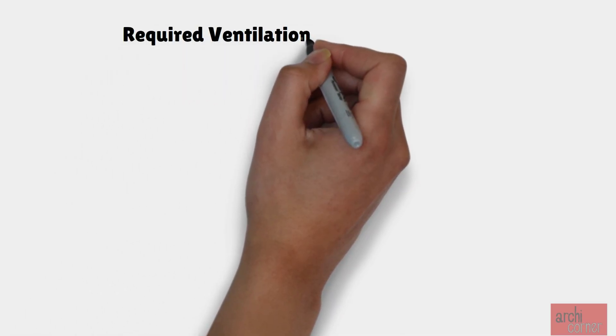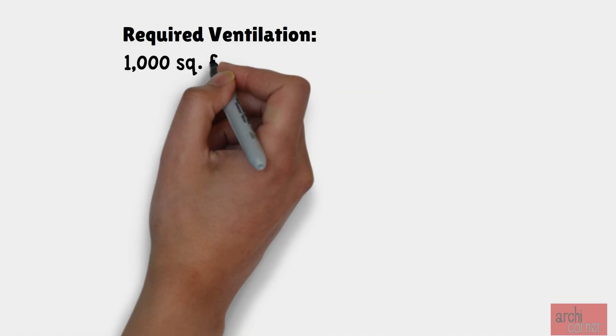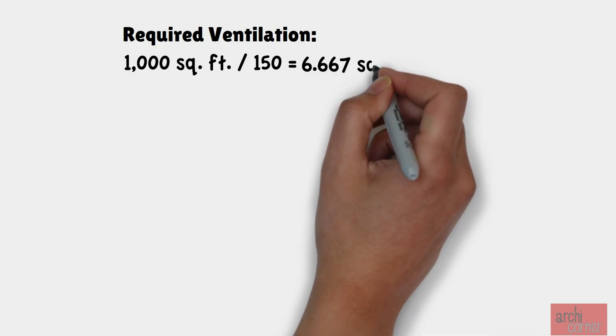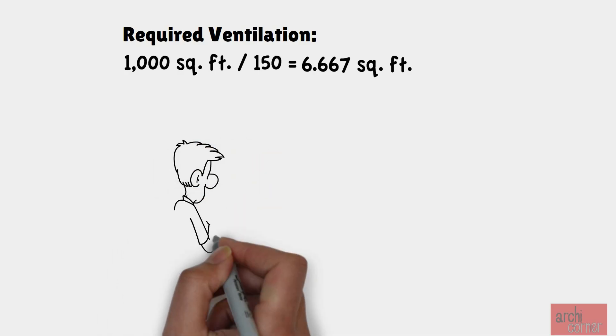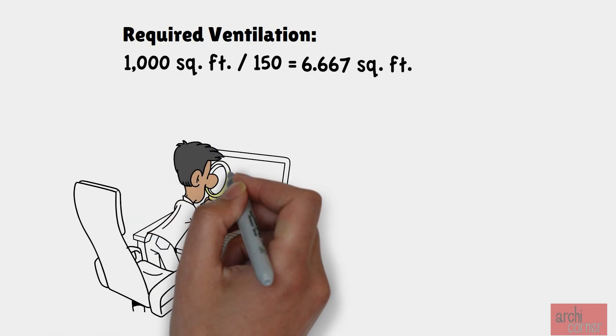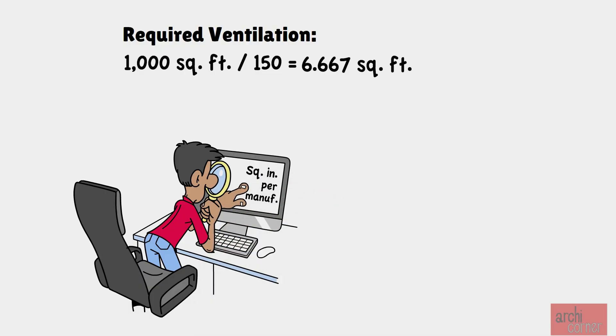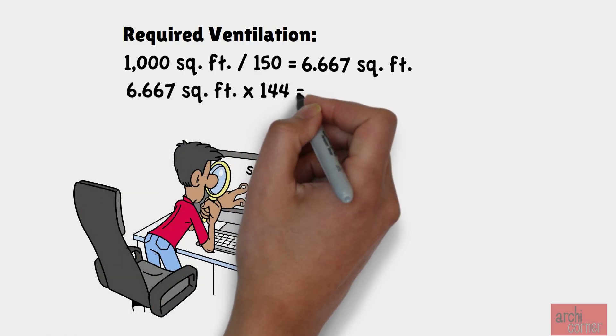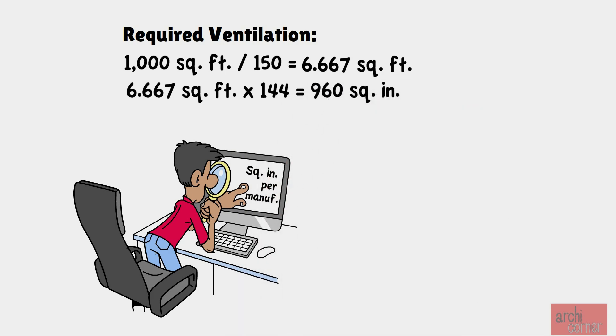The rest of the math is straightforward. We simply divide the area of 1,000 square feet by 150, which provides us with the required ventilation in square feet — in this case, 6.667 square feet. All product information for roof vents usually provides the net free area in square inches, so we convert this by multiplying by 144, giving us 960 square inches as the minimum required venting area.